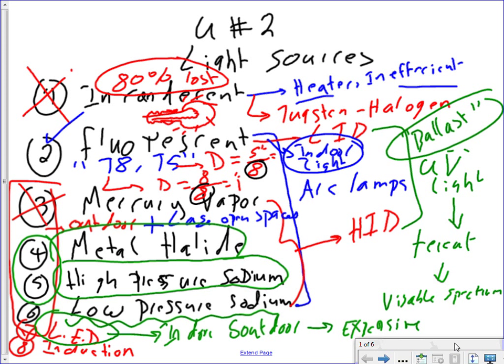So to summarize what we have done, guys, for a commercial building, everything is going LEDs. Next project, guys, all the lights are going to use LEDs. Excluding the LEDs, if you are doing a commercial building, your option number one is going to be fluorescent, indoor. And if you're outdoor, you have two options: either metal halide, the most common, or high pressure sodium. These are very efficient for outdoor areas, as well as warehouses. Metal halide gives you a big floodlight and so forth.